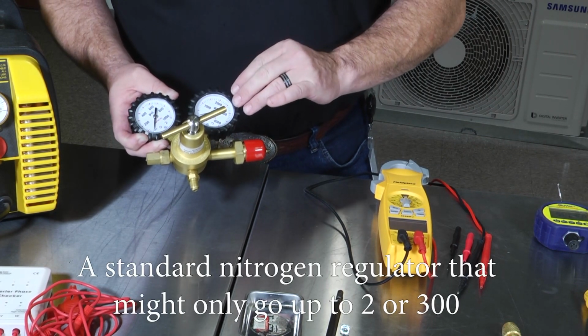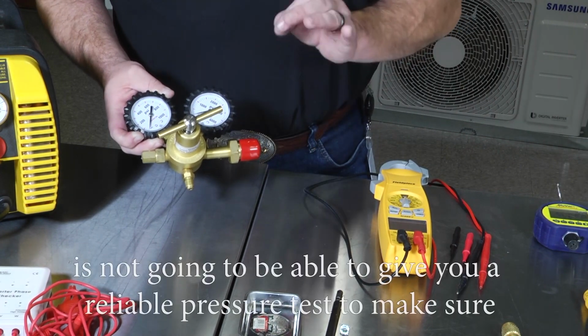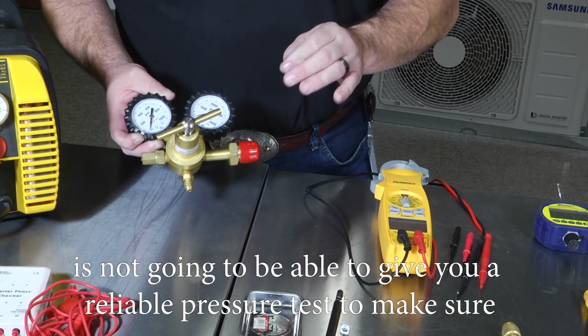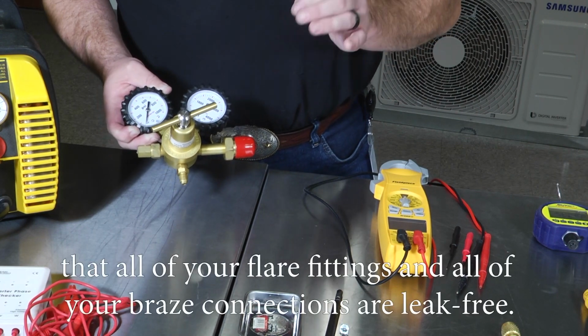A standard nitrogen regulator that might only go up to 200 or 300 is not going to be able to give you a reliable pressure test to make sure all your flare fittings and all of your braze connections are leak-free. This is just a best practice.